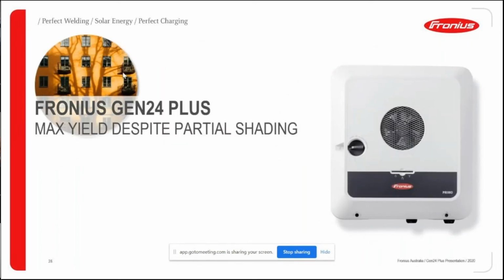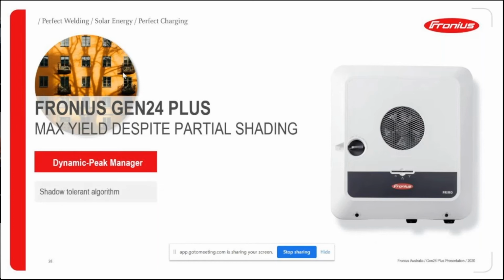And another feature that's been in Fronius inverters for many years now, it's been in the Snap inverters for quite a long time, is the Dynamic Peak Manager. What that is, is just a shadow tolerant algorithm. It's built into the max power point tracker of all Fronius inverters. And this just decreases your losses if you've got partial shading. Something that's brought up quite often is people think that as soon as you shade one panel, the whole string of panels is dragged down. Well, that's not really true, because you've also got bypass diodes in each panel. And with a good max power point tracker, you can really reduce the losses you get from partial shading.